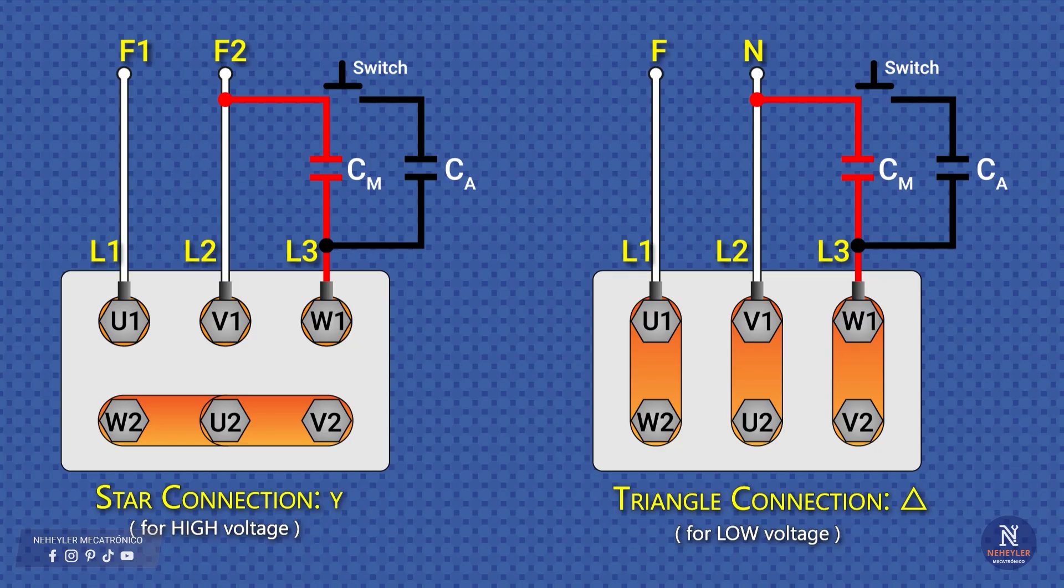When the supply is single-phase, either between two lines or between line and neutral, only two of the three motor terminals receive power directly, and the third is connected through a capacitor. For example, the phase is connected to terminal U1, the neutral to terminal V1, and at the third vertex, W1, we connect the run or permanent capacitor, which remains always in service and is responsible for creating the necessary phase shift so that the motor can start and keep running.